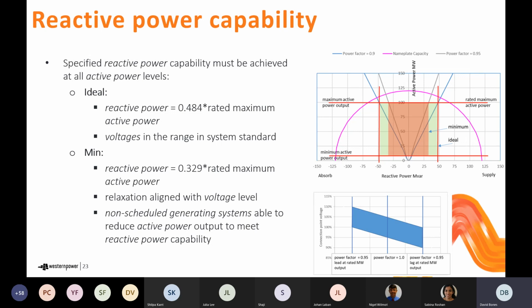So what we're saying there is, in particular, we're comfortable relaxing the requirement if the requirement would not be of particular benefit to the power system. So what are we talking about there? If you think of a power system where the voltage is between 1 per unit and 1.1 per unit, so you've got high voltages, under those conditions you really want to be able to absorb reactive power and control those over voltages. Being able to produce reactive power at that location under those conditions is probably not going to be required. And so there's that relaxation.